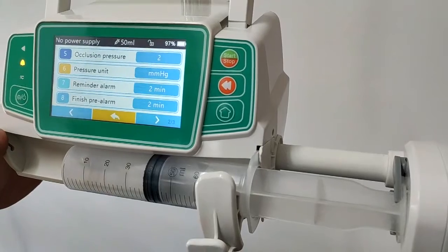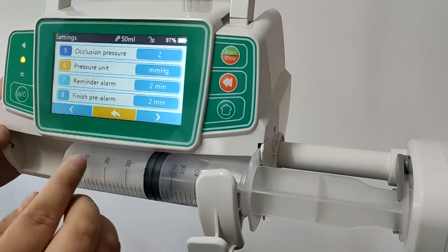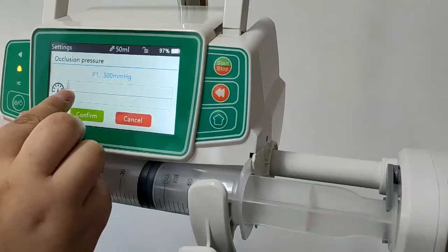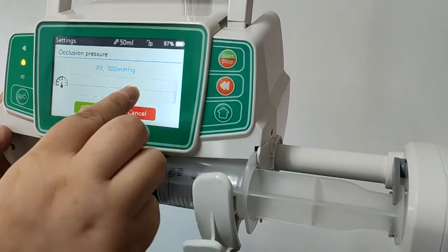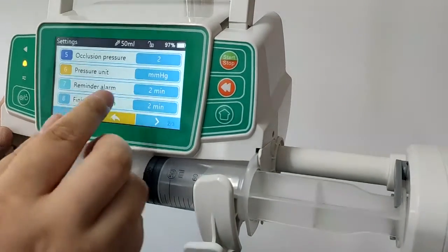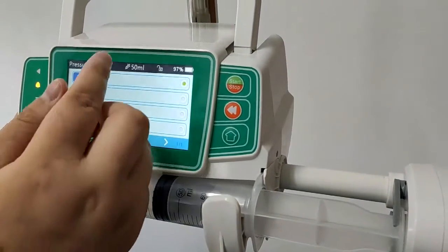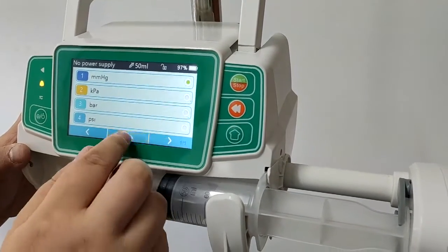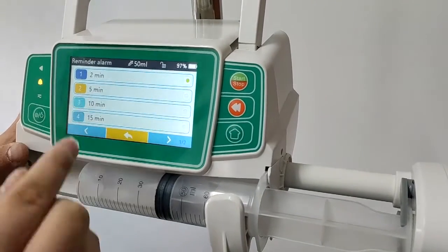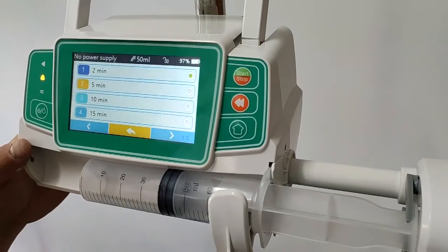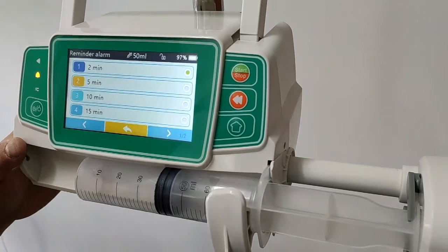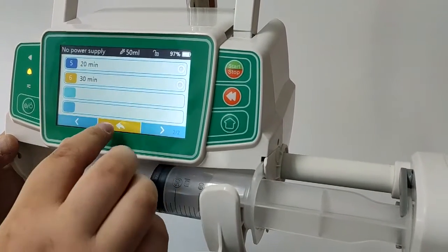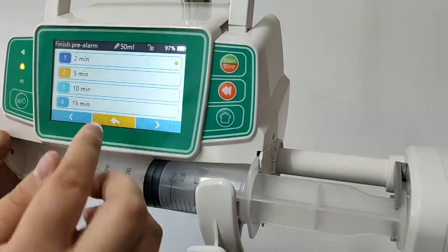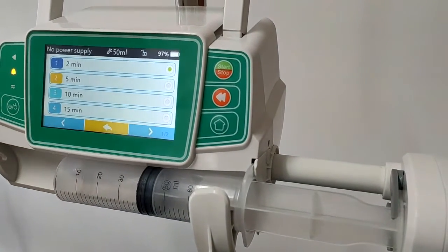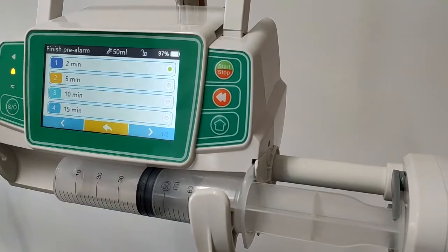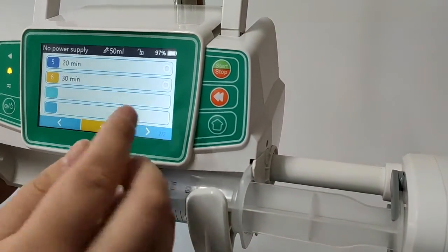And by the second page of the settings, you will find the occlusion pressure. For this model, you can choose from the pressure level 1, 2, 3. The default one is 1, 2. And then you can also change the pressure unit. And here, the reminder alarm. It will remind you not using the pump after you set the parameters to remind the loss. Now you can choose different times. And the finish pre-alarm means to remind you the pump is going to finish the VTBI, before maybe 2 minutes to 30 minutes.